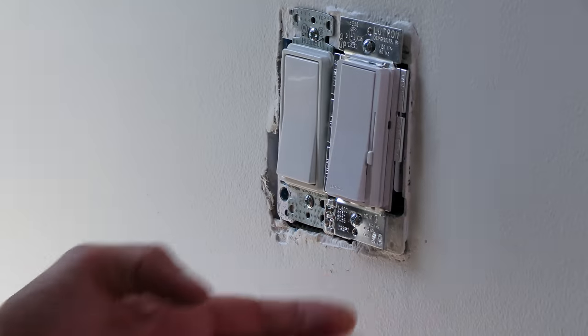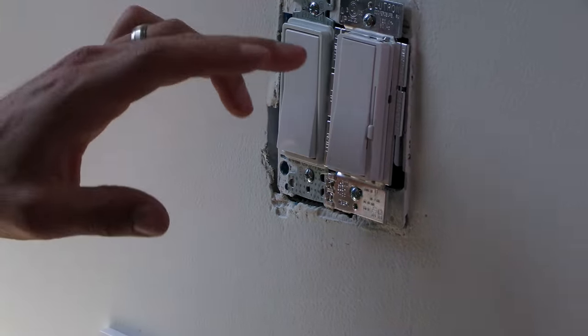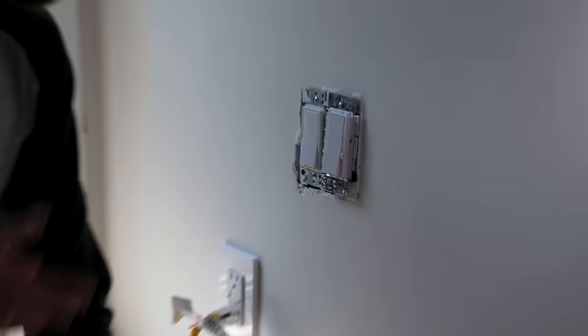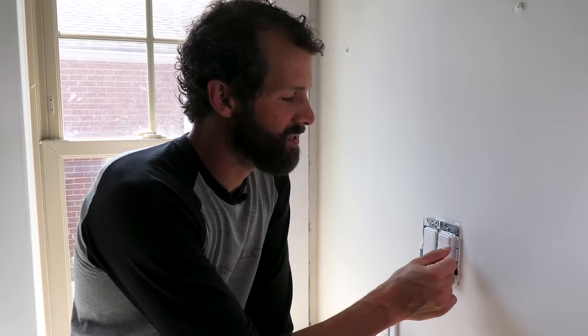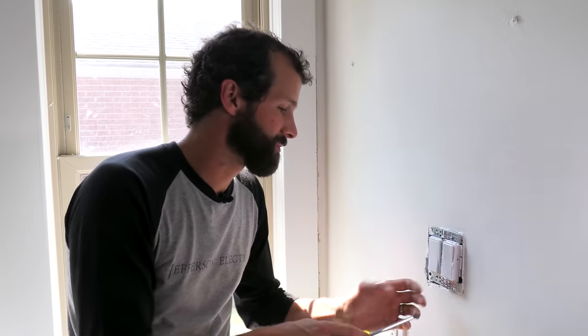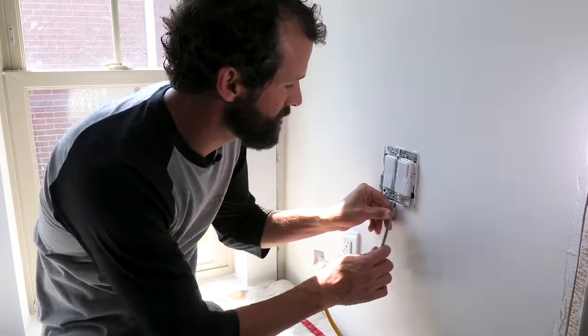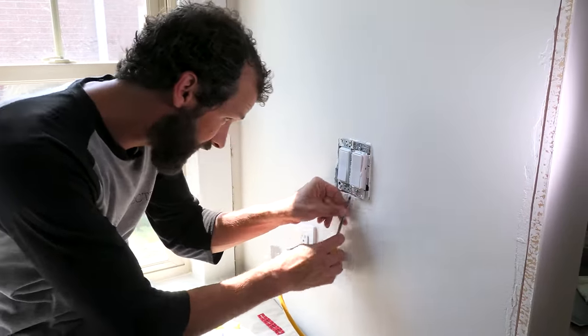Note this too, if you short on the load side of the dimmer, the lighting side of the dimmer, you'll blow the dimmer out. And sometimes you'll lose total functionality depending on the dimmer, but sometimes you'll just lose the dimming function. There can be a variety of situations. And so if the dimmer is working as a switch and not as a dimmer, it probably got blown. And they're real sensitive, so you could blow the dimmer without blowing the circuit. It is possible.